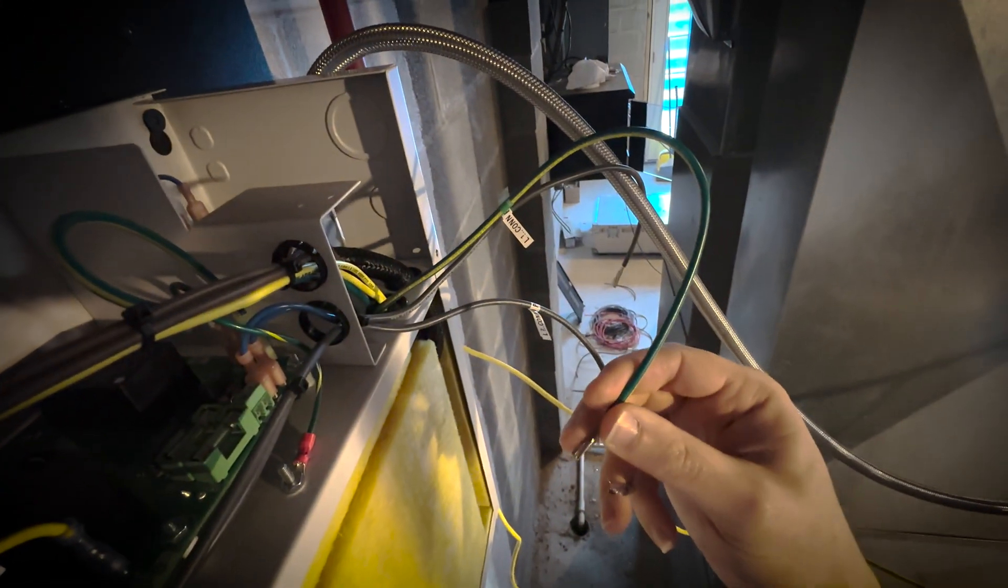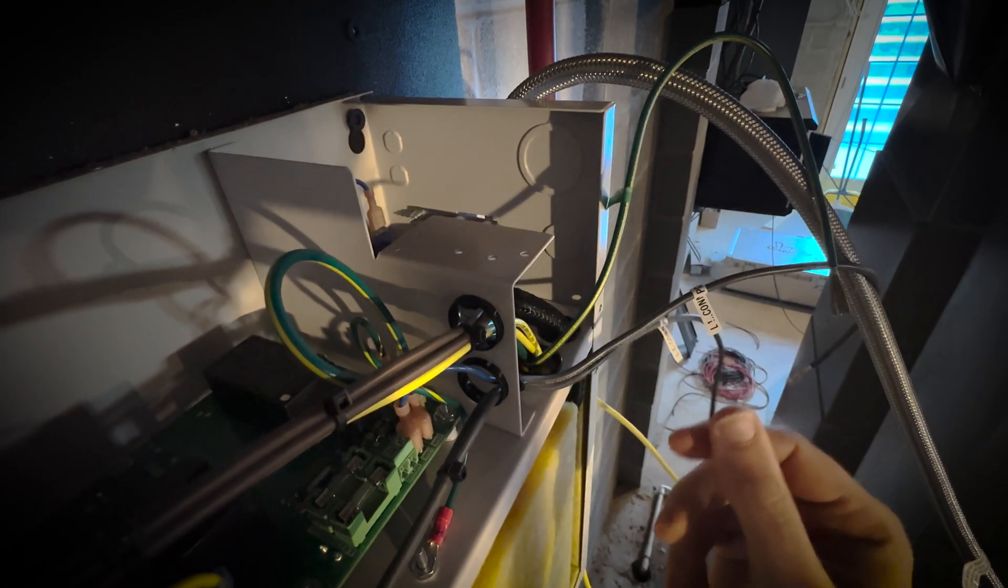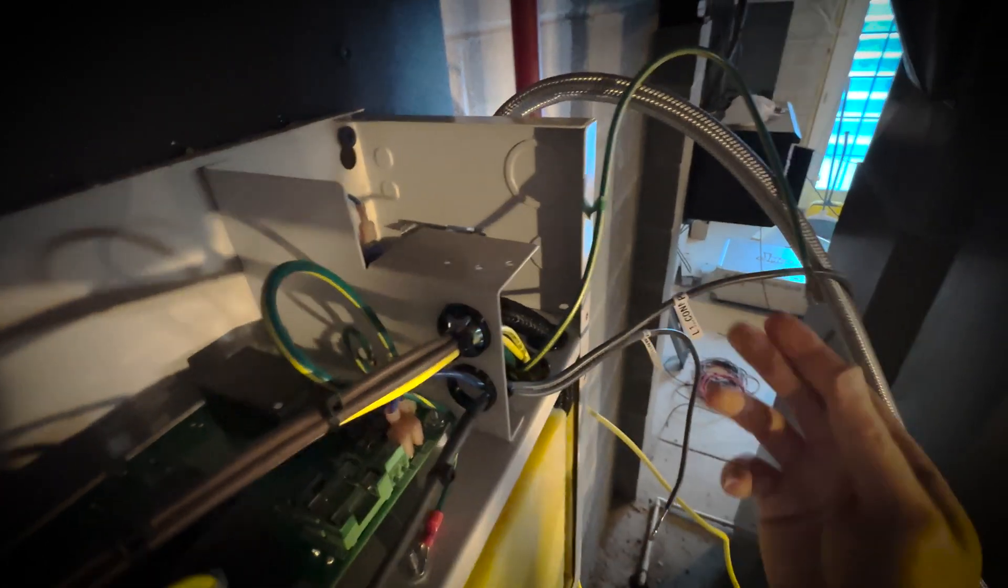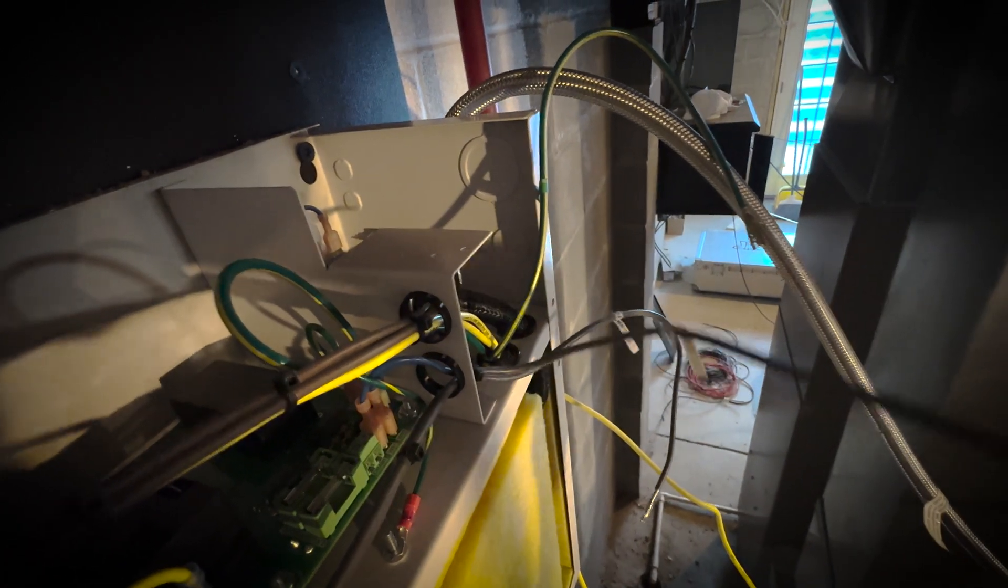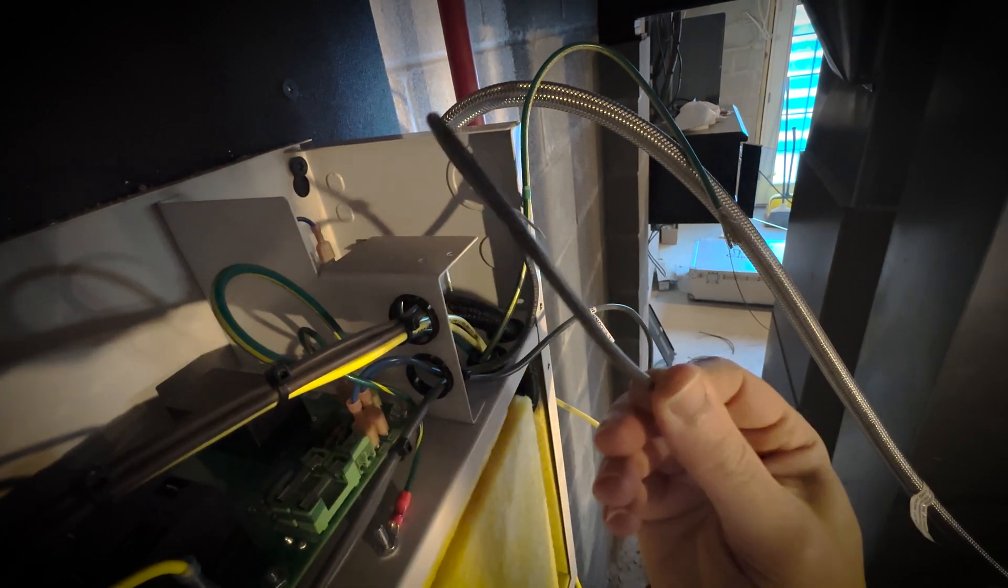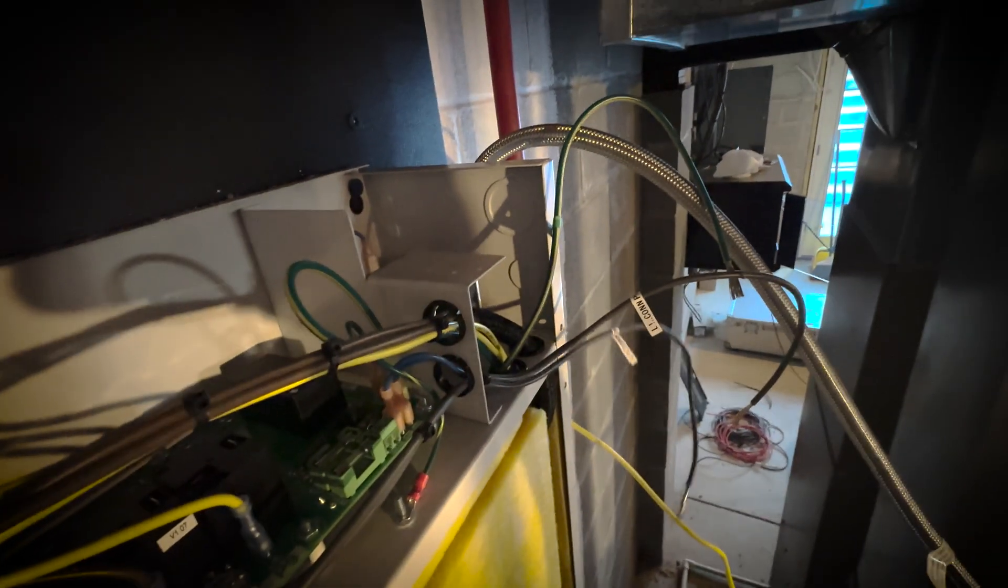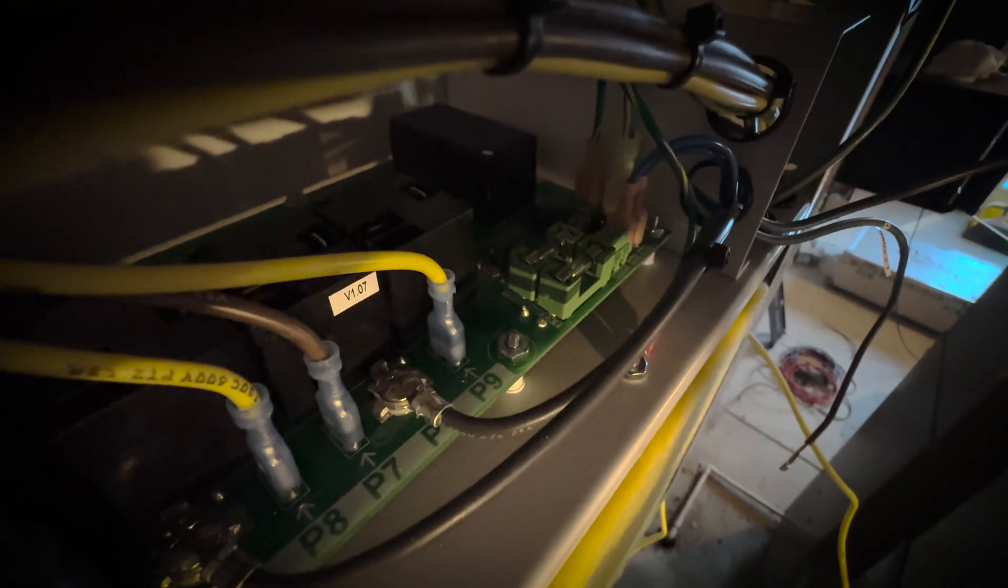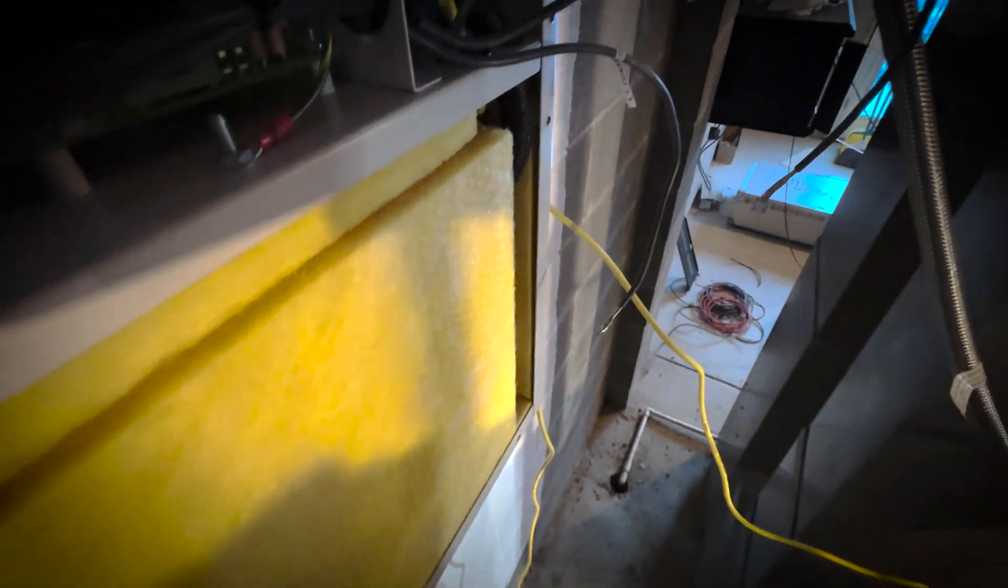That's interesting. This wire feels awful thin. This feels like 10-gauge wire. Trying to see if I can read on the side here. Yeah, this wire doesn't feel particularly thin. If I was a betting man, I can't really read the description on the side. It feels kind of weird. But none of this is very thick. I would say that because it's flexible, it's probably 10-gauge wire. But it needs a double-pole 30-amp breaker. And I ended up buying 8-gauge wire just to get over to it. But it does not appear that it needs a neutral. There's little fuses on the board there. Yeah, so it just needs L1 and L2.